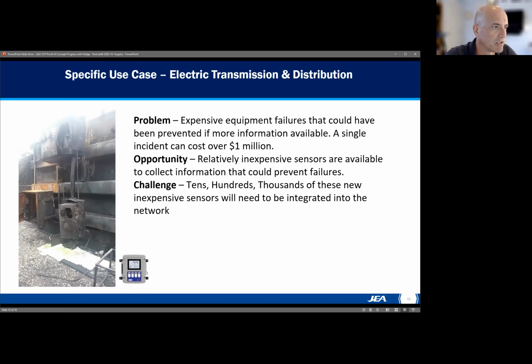We've got a picture here on the left of a transformer that exploded. There was an undetected problem. The control system that controls this, the SCADA system, doesn't monitor things like dissolved gases from the oil and detect arcing. It's not looking at whether fans are working and things like that. It's opening and closing breakers and measuring the amount of current and power going through it.